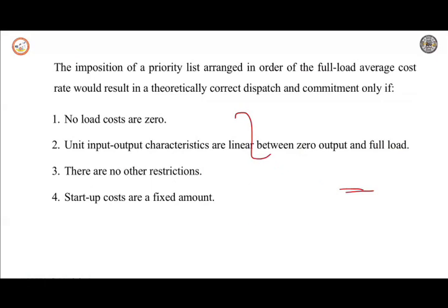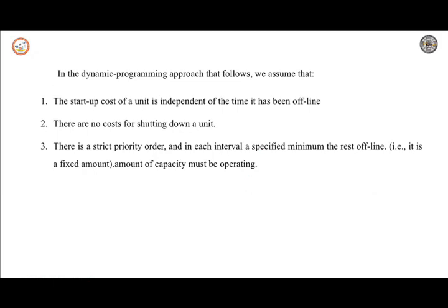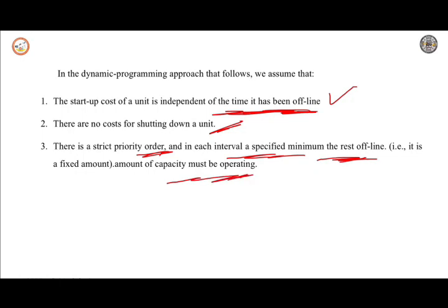In this method, there are a few assumptions, in addition to those made in the priority list method. The first assumption is the startup cost of a unit is independent of the time it has been offline. The second point is there are no costs for shutting down a unit. Third, there is a strict priority order, and in each interval a specified minimum amount of capacity must be operating.